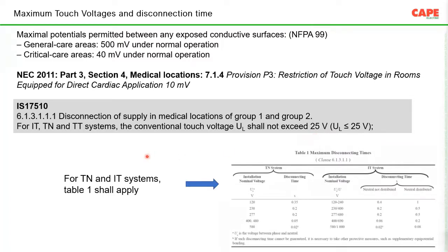Table 1 of the same IS standard says for general location, we are supposed to use a TN system, and the disconnection times are given. Also the IT system disconnection times are established. If you carefully look into this table, what is missing is a TT system. So we are not supposed to use a TT system in a normal application. TNS is recommended in IS 17512. I'm sorry that I put 17510 somewhere. That is a mistake. 17512 is the correct standard. So basically, TT systems are not recommended in medical locations or in the hospital.